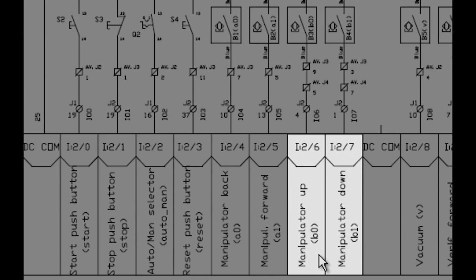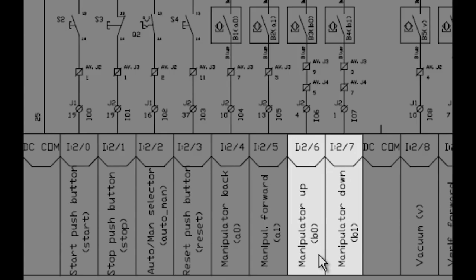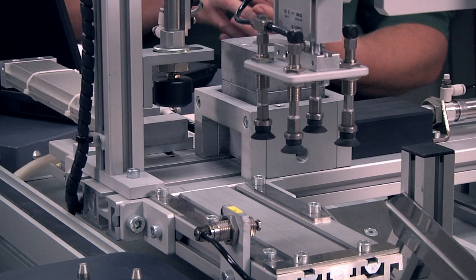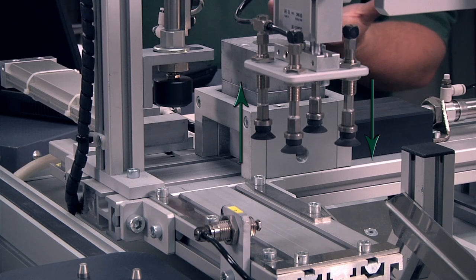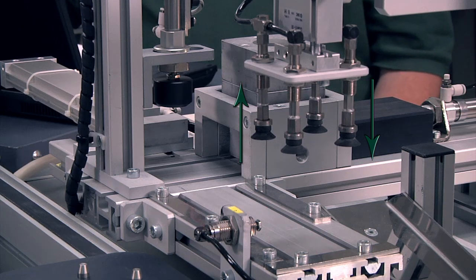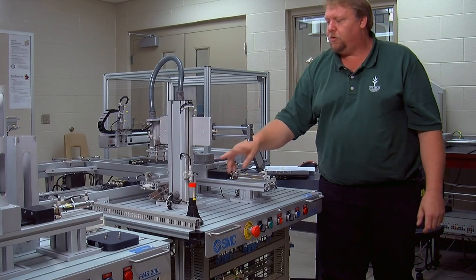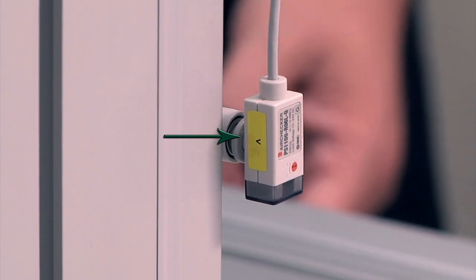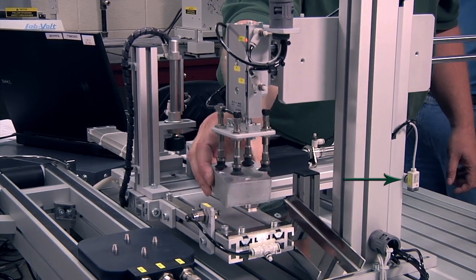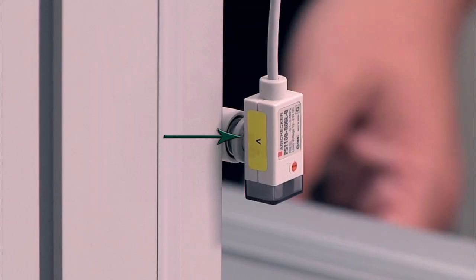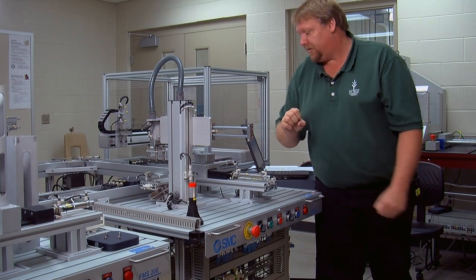Our next input is manipulator up and down — that is I:2/6 and I:2/7. I:2/6 is in the up position; I:2/7 is in the down position. And the next one is I:2/8, which is a vacuum sensor. When the body is actually attached here by vacuum, this sensor is going to be triggered, letting it know that vacuum is present.